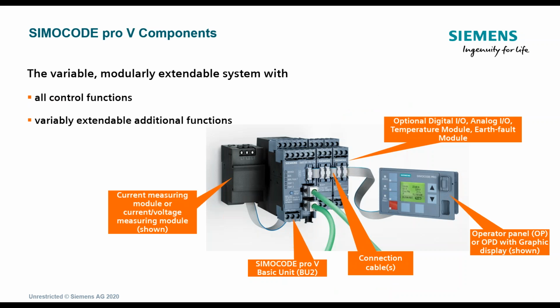And then we have the ProV, and here are some of the components of it, the higher end one. So please understand, you remember I said that our CT PTs are not integrated into the system. It's not all one piece, it's a separate piece. So there's a cable that leaves the CT PT and goes over into the SIMOCODE. That cable can be up to almost 7 feet, 6.5 feet, and we can go up to 630 amps measurement. And then you can see we've added on. Now the basic unit, if you called me today and said, Mark, I've got an application for SIMOCODE, I would ask you for the full load amps of the motor, and then I'd ask you for the control voltage. But the part numbers that I would give today would be 3.